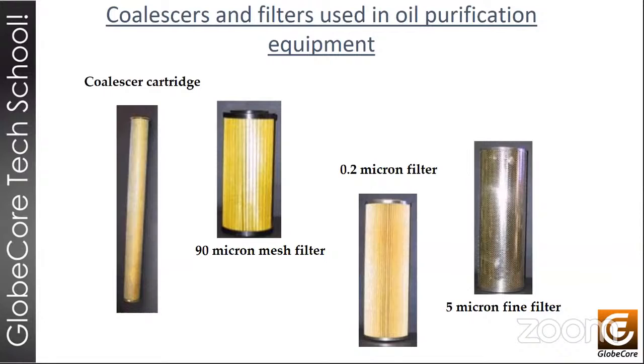It's not recommended, of course, to wash these filters when working with transformers, at least with water, because water is sometimes used to clean these filters, but obviously when using water, it's quite problematic because water can and will contaminate the dielectric oil. So for these types of filters in this application, the best way to clean them is with the same type of dielectric oil that flows in the reverse direction. And obviously the oil that we use to clean the filters should not be reused because it will be saturated with solid particles and it should be safely discarded. Next slide, please.